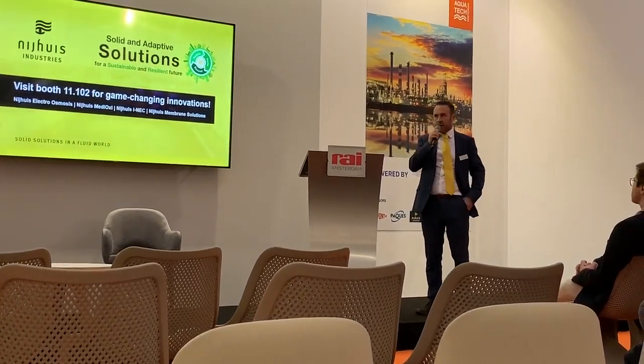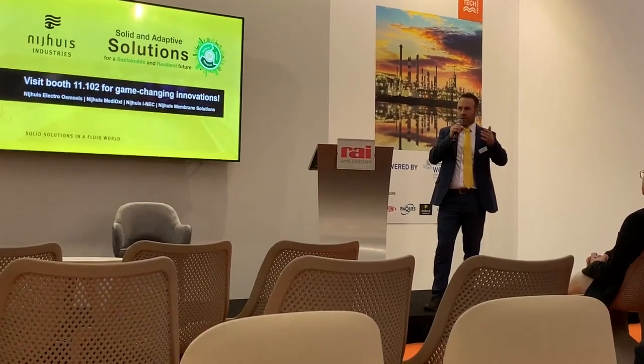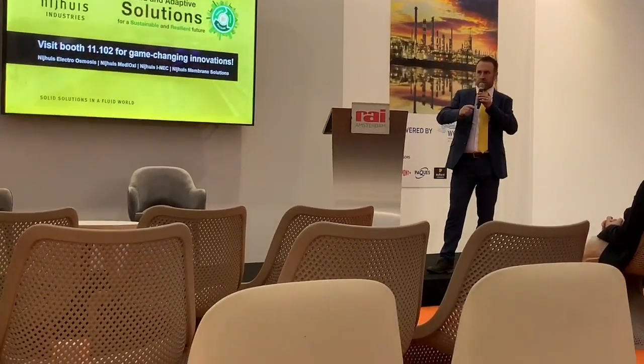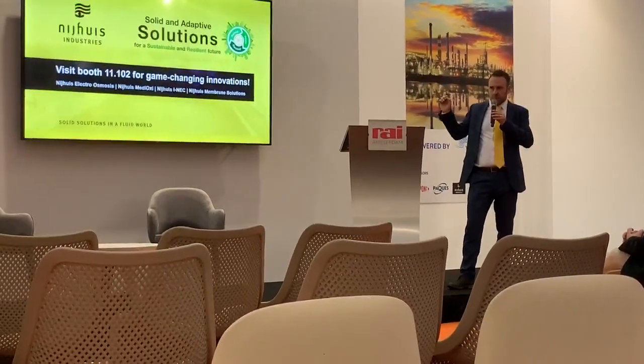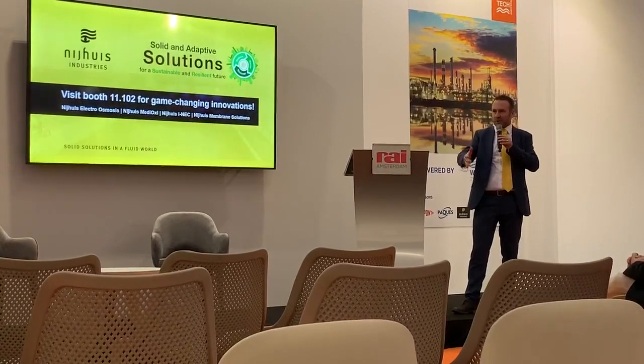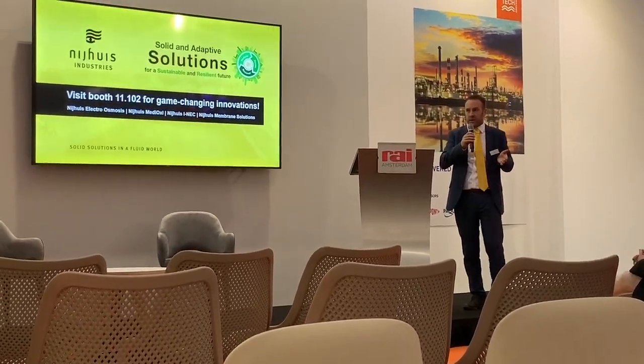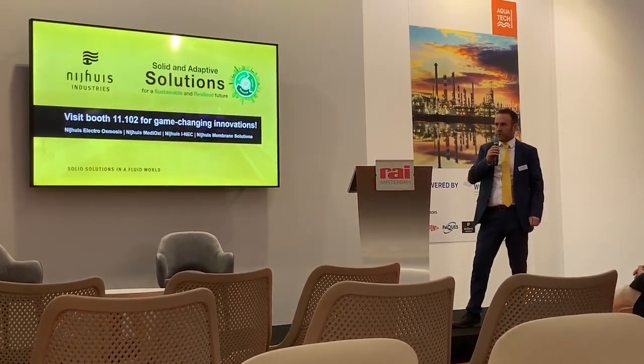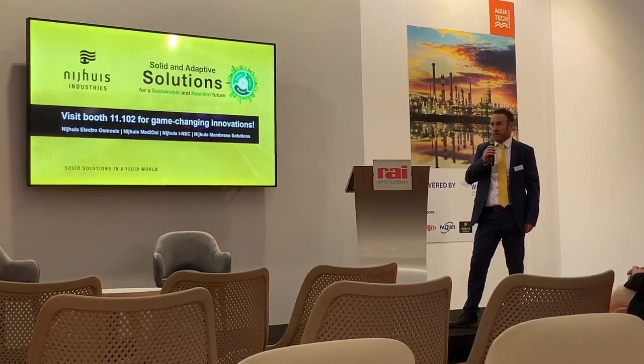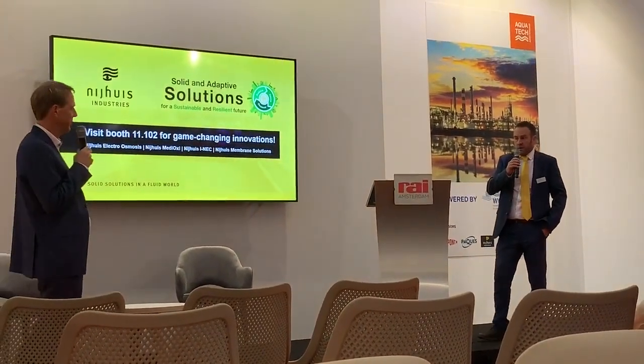In this particular case, what we found initially, when the system was being cleaned up, was that it was actually more difficult to control general bacteria. We seemed to get rid of all the biofilm, and that uncovered a whole host of additional things, pseudomonas and lots of exotic bacteria. After 3 days, once the biofilm had gone, the control was much better in terms of just general bacteria. Initially, you got an increase in bacteria, but then your situation became under control.